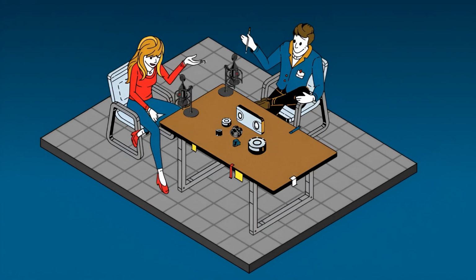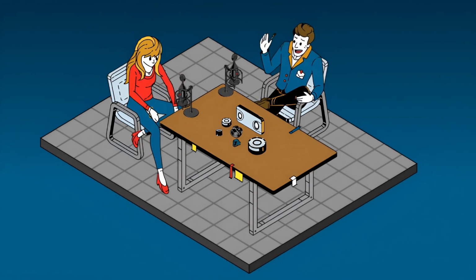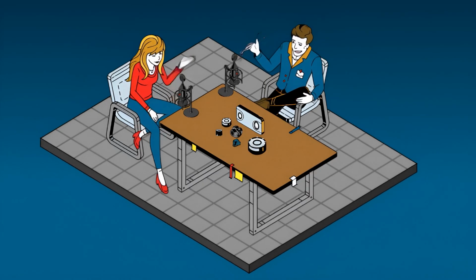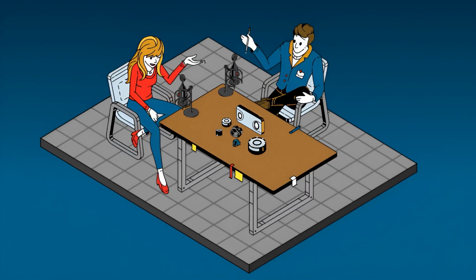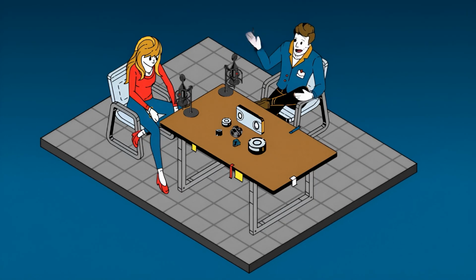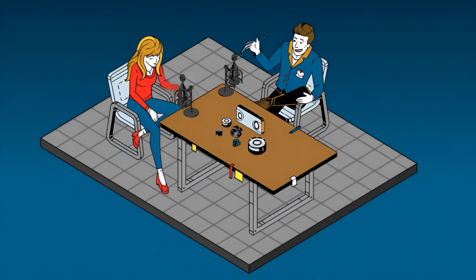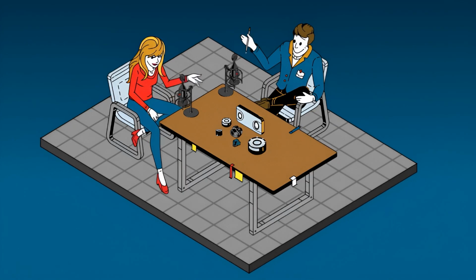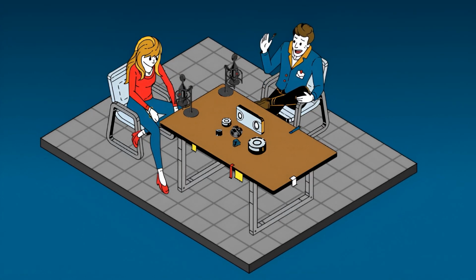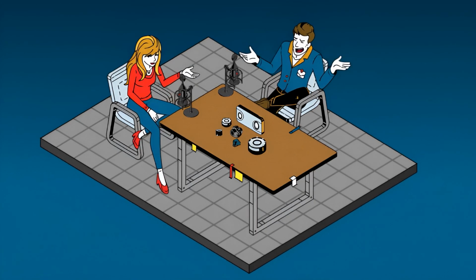There are other benefits too. The design gives a higher electrical output signal, which is cleaner and easier to read accurately—a better signal-to-noise ratio. It also has much better fatigue life, handling countless load and unload cycles without performance degrading, which is crucial for long-term testing or industrial use. Plus, its inherent resistance to side loads, those extraneous forces, is excellent, which is vital in the real world.